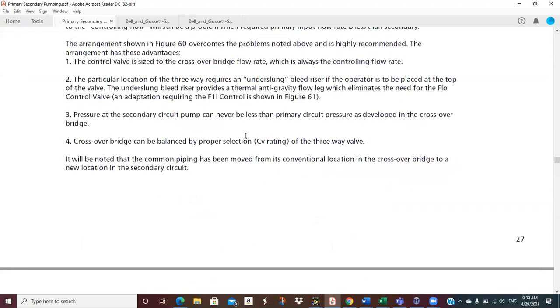Okay, so that makes sense. The particular location of the three-way valves requires an underslung bleed riser if the operator, and this is on the control valve, is to be placed at the top of the control valve. Okay, that's really getting down into the details of it. But the underslung bleed riser provides the thermal anti-gravity flow leg and eliminates the need for a flow control valve. So we remember that from the underslung bleed riser discussion, hopefully.